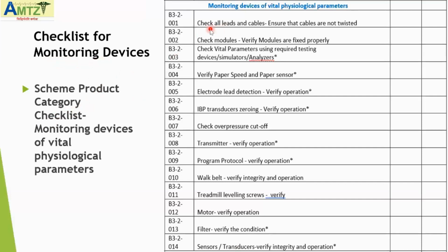You can see the first point: check all the leads and cables, that is, ensure that the cables are not twisted. You are just checking whether the cables are in good condition or not, and a simple multimeter can get the job done. A continuity test can clearly ensure that the cables are all in fine condition. The third point is to check vital parameters using the required testing device, simulators or analyzers.